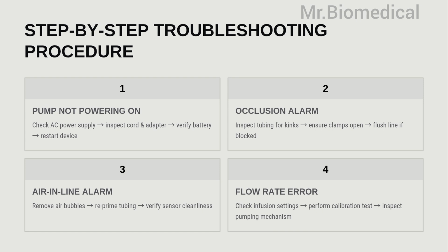Now let's see the troubleshooting procedure. First, if the pump is not powering on, start by checking the AC power supply, inspect the power cord and adapter for damage, verify battery condition and ensure it is charged. Finally, restart the device and observe its response. Second, occlusion alarm. Inspect the tubing for bends, kinks, or a blockage. Ensure all clamps are open. If necessary, flush the line to remove any obstruction.